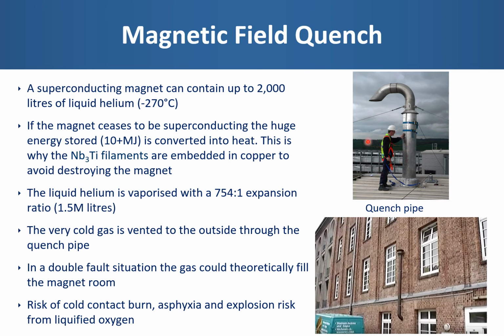I certainly hope that this quench pipe actually isn't connected to a magnet, otherwise I certainly wouldn't want to be standing there. There have also been situations whereby the helium gas has vented into the magnet room, and in at least one situation the pressure overload in the room has prevented the inward opening magnet door from being opened. Therefore, the current advice is that all MRI magnet doors should open outwards.